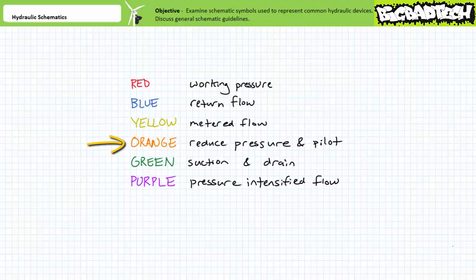You'd think using the same color for two different flows would be confusing, but it isn't. An example of pilot flow would be to the dashed pilot input of a pilot to open check valve. An example of reduced pressure flow would be the solid outlet of a pressure reducing valve, a common pressure control valve we'll examine in later lectures.